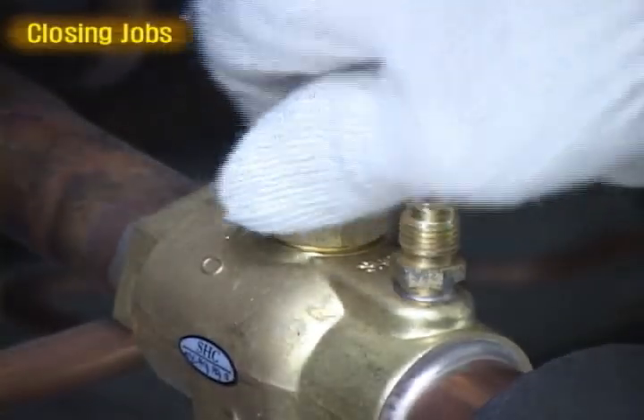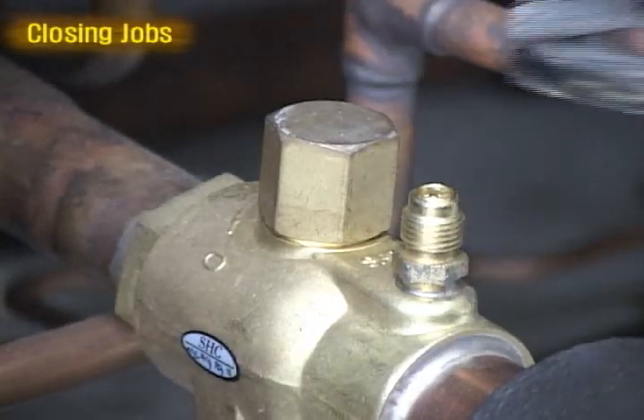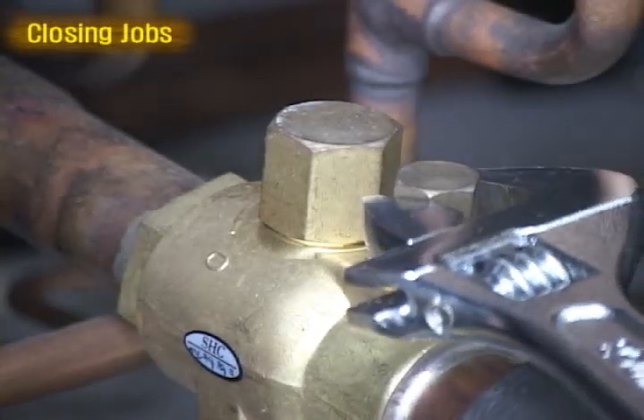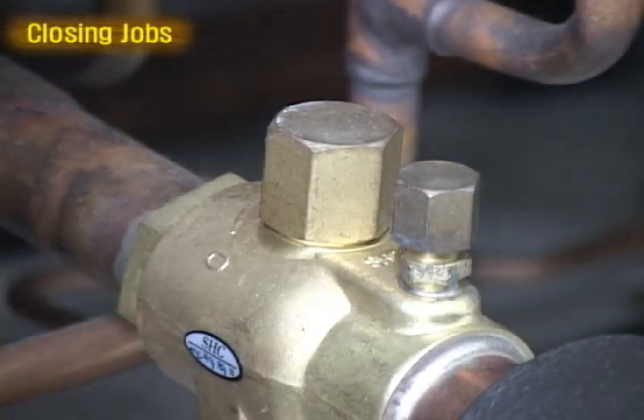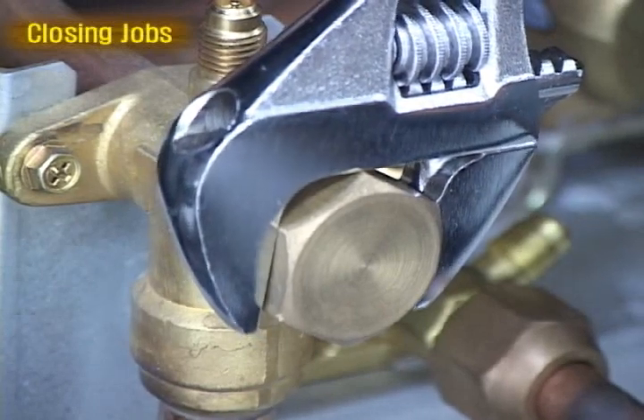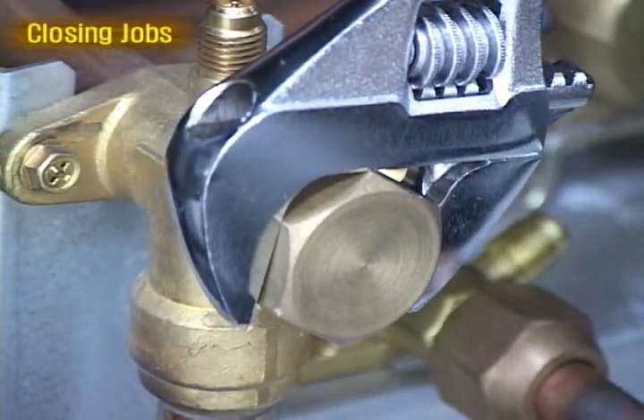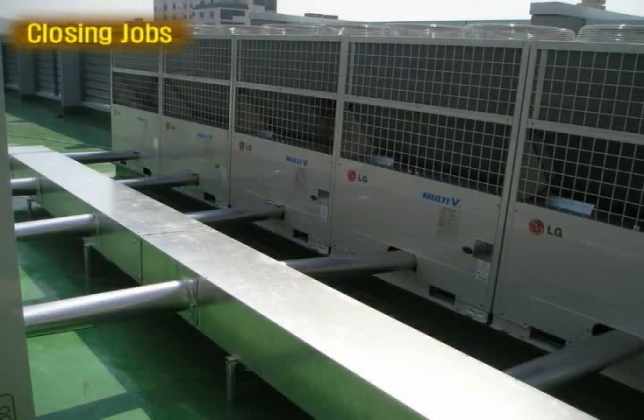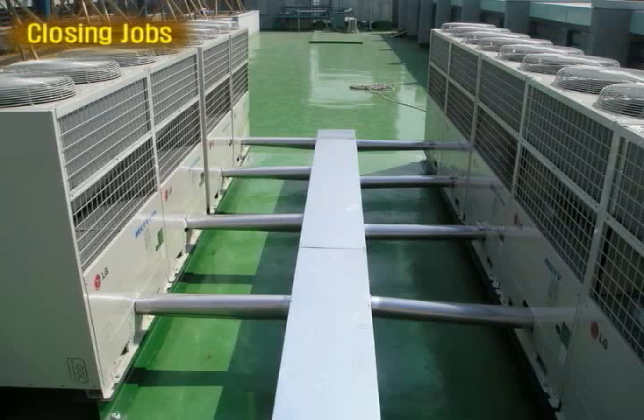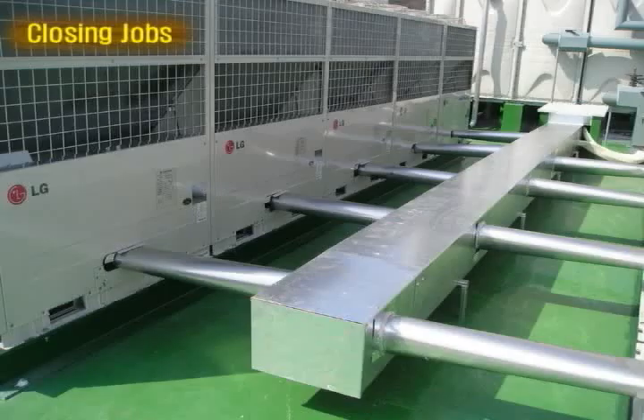Connect service port cap and valve cap of high-low pressure shared pipe and service valve of indoor unit. Fasten every cap of service valves and service port. In order to protect exposed pipe from outer environment, fix the pipe tray cover. Clean the indoor and outdoor installation site and collect the garbage.